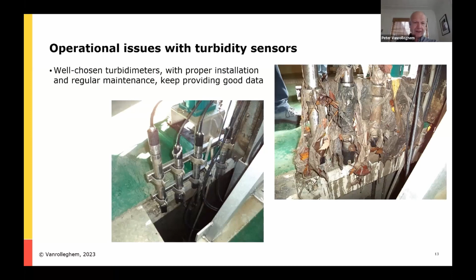We all love these TSS-turbidity relationships, but we know they are wastewater dependent, time dependent, location dependent, and basically particle optical property dependent. So we have to calibrate regularly. People don't care too much about it because they're mainly interested in dynamics, in seeing when things are happening, not in absolute TSS values. But if you want to really get TSS values in an absolute sense, you must do regular calibration.